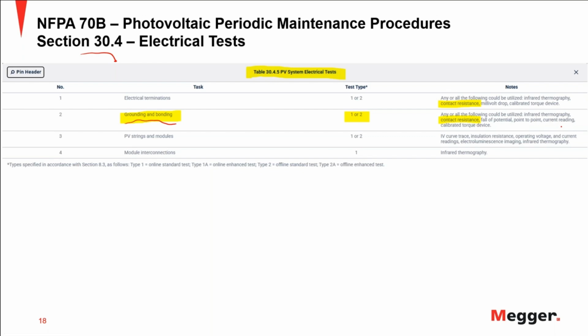All of these methods are going to give you some idea of whether the connection is good or not. Especially infrared thermography, it's only going to help if you have current circulating through the connection. If there's no current, infrared is not going to tell you much. And torquing is not necessarily giving you a good connection. If you have some contamination, or some foreign object between the connection, you could torque it very well, but it's not going to give you the right resistance for that surface.